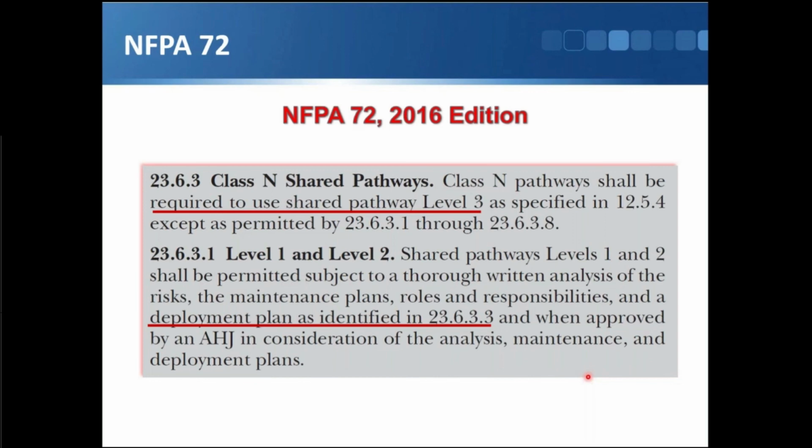So anyway, 2016 said you don't have to, and somewhere in the annex, it had a clarification line that says you don't have to have them physically separated. Well, that was changed in the next edition. So in the 2019 edition, you have to have it. It's the same rule that you would use for a Class A or X system on that separation.